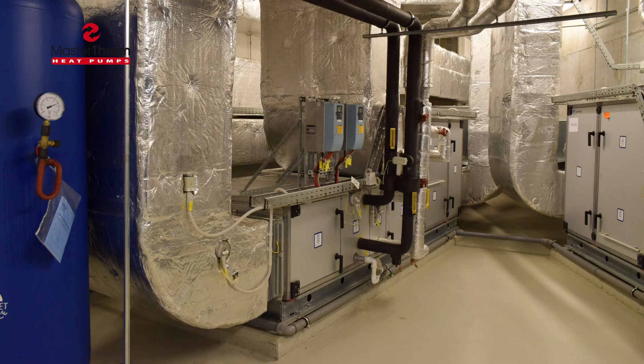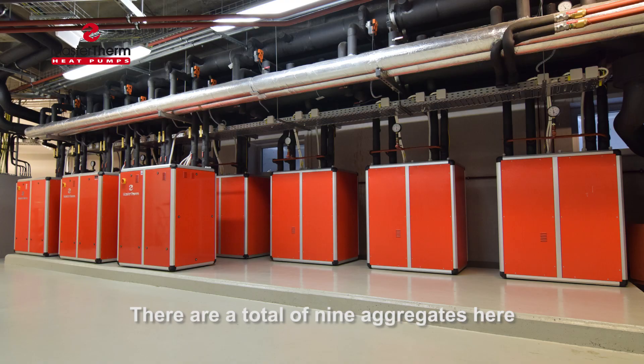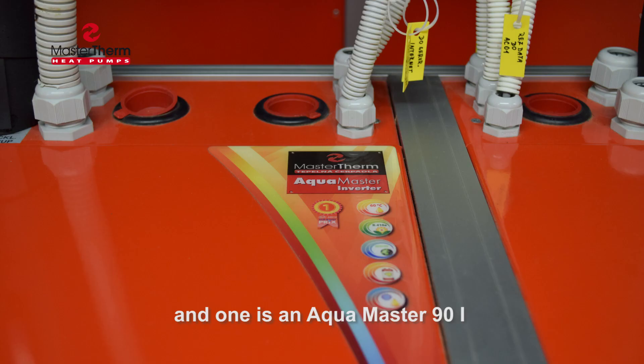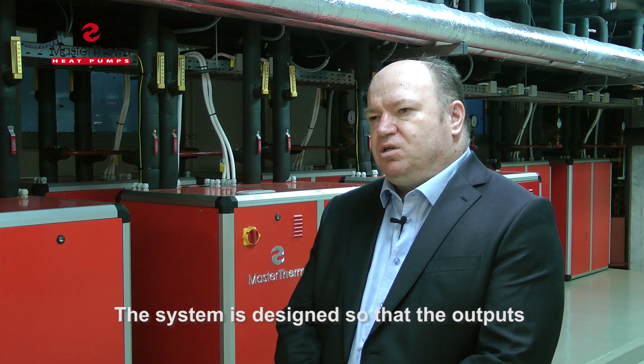To precisely manage cooling capacity for air conditioning, the system is equipped with a variable speed compressor unit. There are nine aggregates in total: eight are two-compressor aggregates of type Aquamaster 180Z, and one is an Aquamaster 90i with a wide operating range.